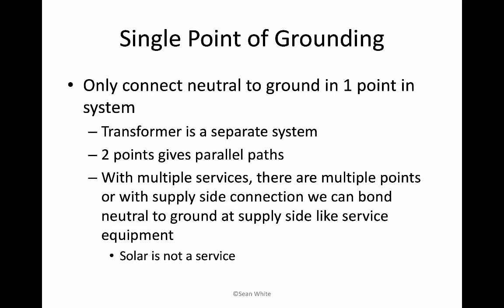So besides a transformer qualifying something as a separate system, if you had a big building and you had different transformers changing the voltages in your giant big building that you're putting solar on, that would be one way of doing things. But another thing is if you have multiple services, like a building with different tenants, then in that case, you also can have multiple points of system grounding. So it's like having a separate system if you have, say, a separate meter.